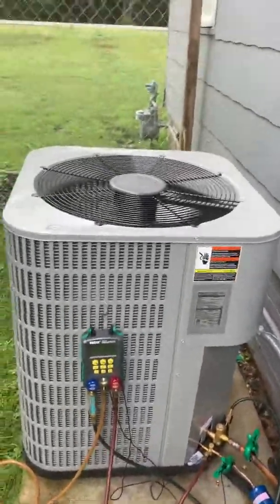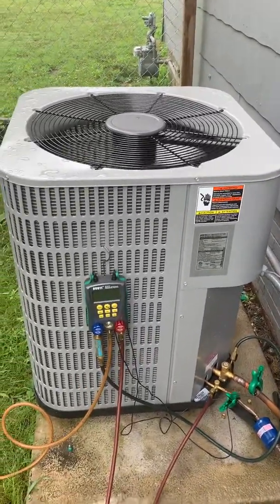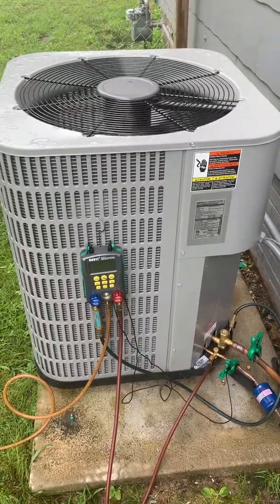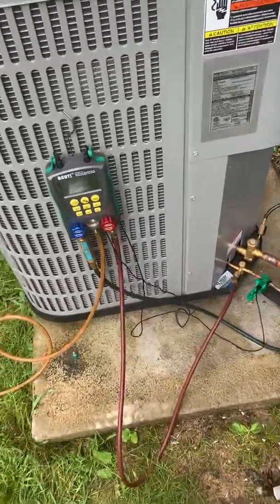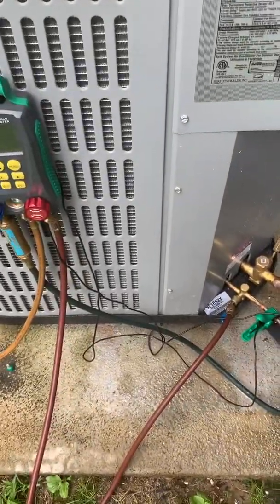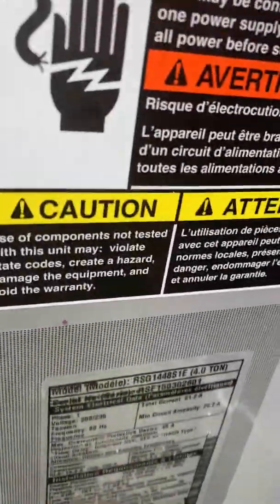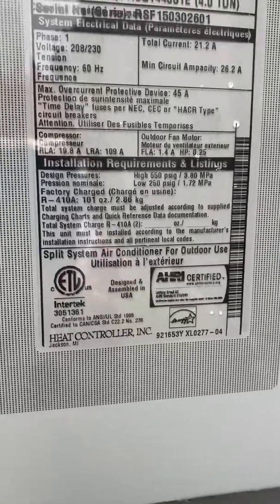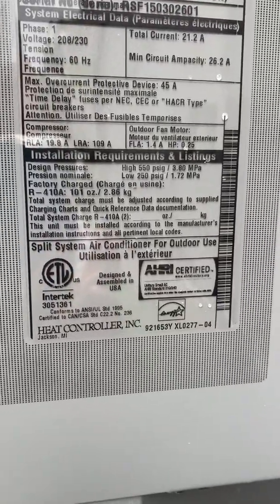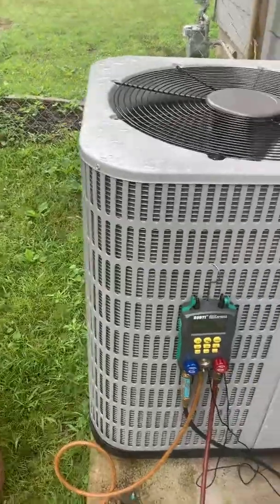What's up YouTubers. I figured I'd make a video here - I've seen many articles online on YouTube on how to recharge R410A in one of these units. Let me give you a little background: I just got this unit, it's a model RSG144B51E. It's R410A. If you look at this rating plate right here, nowhere on this rating plate do you see anything with a subcool or a superheat. What they did is the book came with a little chart here.